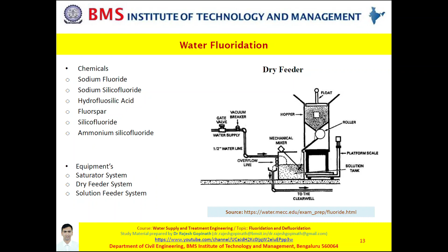The saturator system, the principle employed here is 4% of sodium fluoride is produced and injected at desired concentration at the water distribution source with the aid of a pump. When it comes to the dry feeder system, the principle is sodium fluoride or silicofluoride in the form of powder is introduced into a dissolving basin with the aid of an automatic mechanism. The third one, solution feeder system. Here the principle is the volumetric pump which permits addition of a given quantity of hydrofluorosilicic acid in proportion to the amount of water that has to be treated.